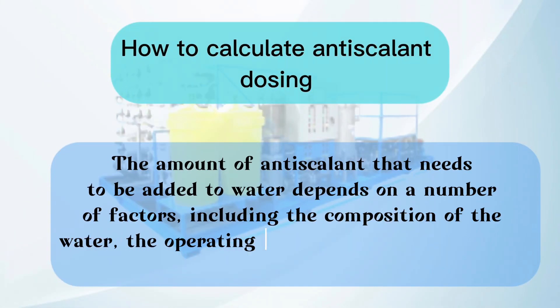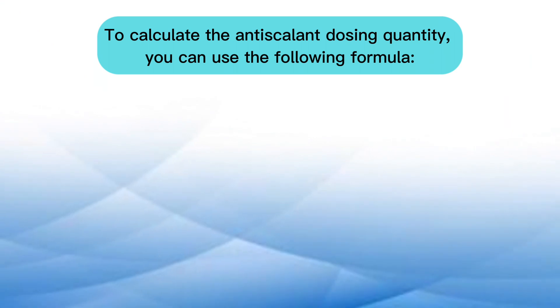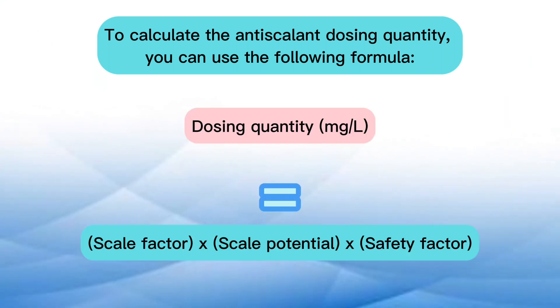How to calculate antiscalant dosing quantity. The amount of antiscalant that needs to be added to water depends on a number of factors, including the composition of the water, the operating conditions of the RO plant, and the type of antiscalant being used. To calculate the antiscalant dosing quantity, you can use the following formula: Dosing quantity (mg/L) = Scale factor × Scale potential × Safety factor.